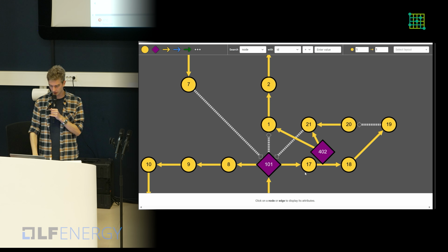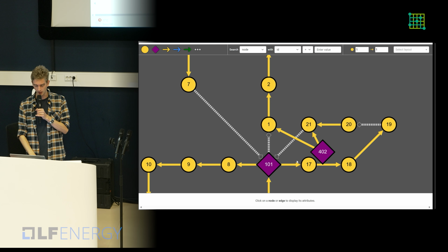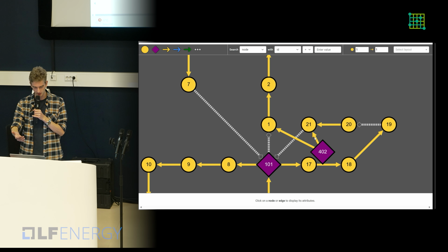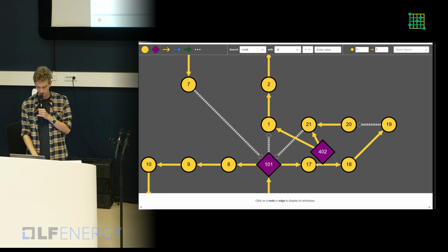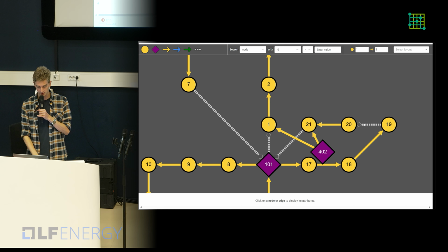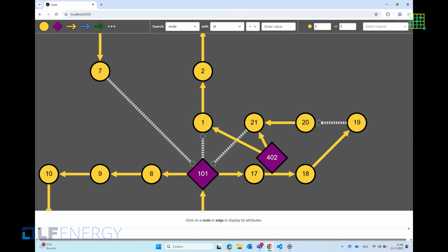If we take a look, previously the route with node 17 was congested, right? Now we have created a new cable from the substation. That's this yellow cable, but just right now when we were doing the exercise, this cable was inactive. Using the optimization, we have determined that it resolves the congestion if we open this existing cable and then we close this cable.